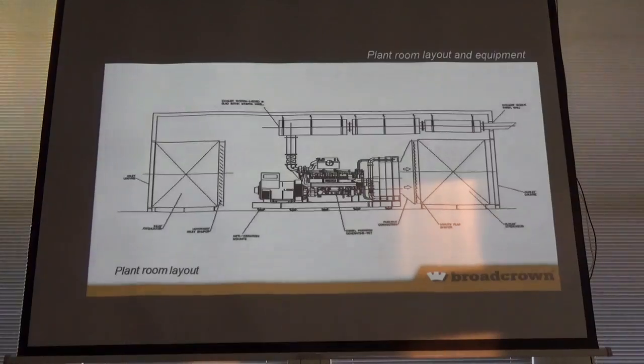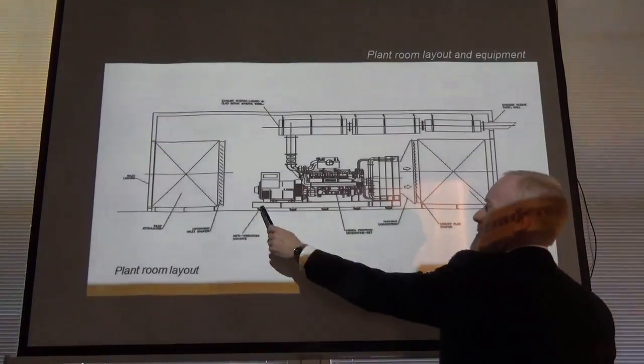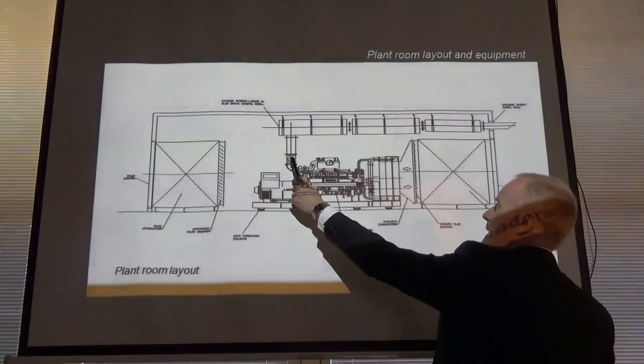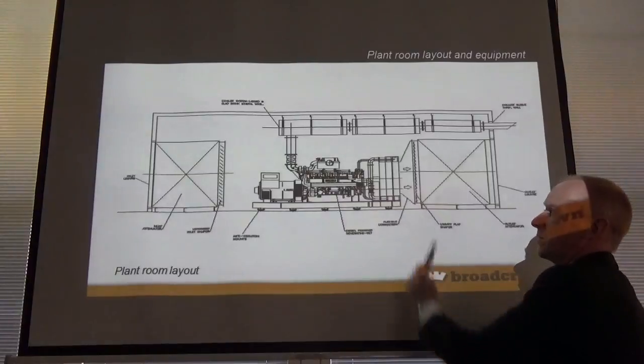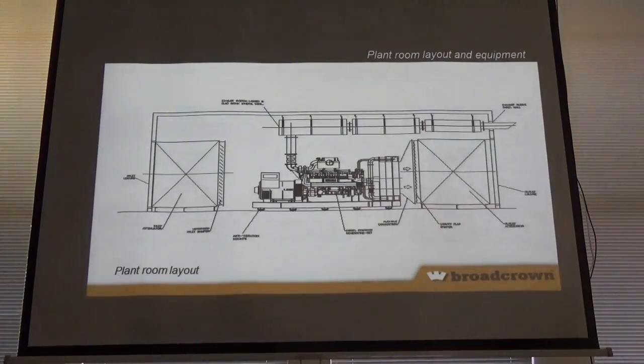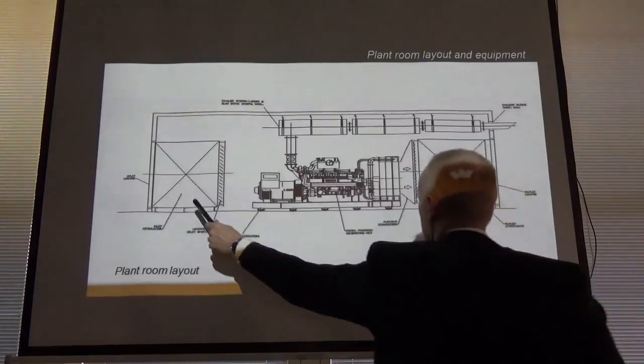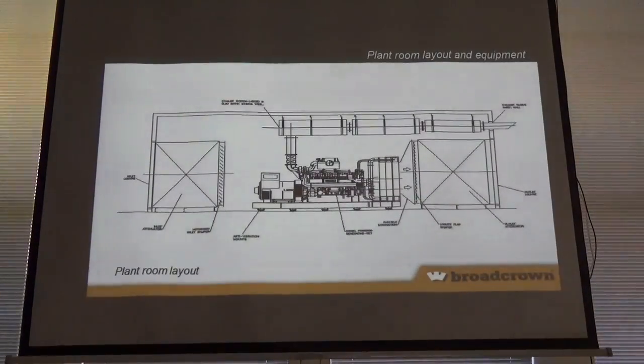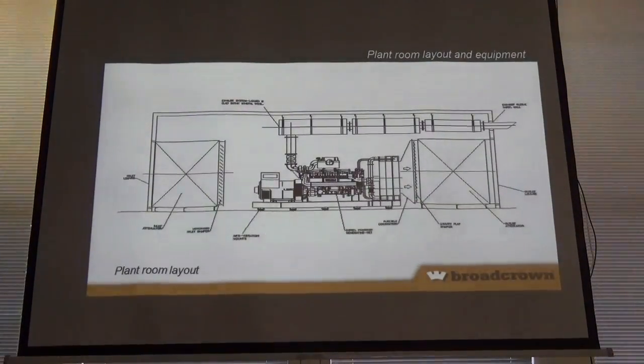So, in a plant room application, notice the genset itself, it's isolated. It's mounted on AV mounts here. You've got a bellows here. You've got a flexible canvas here. So it's isolating the noise generation, the vibration source as best it can so it doesn't transmit through the building, the structure itself. The size of the inlet attenuator and the discharge is dictated by a combination of two things. It's a function of cross-sectional area required on the inlet and discharge and length of attenuator.